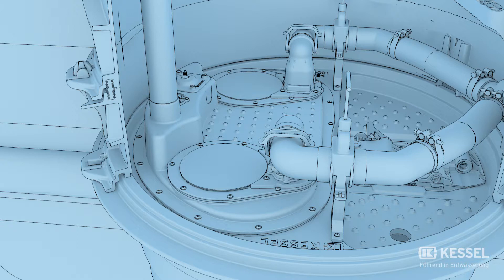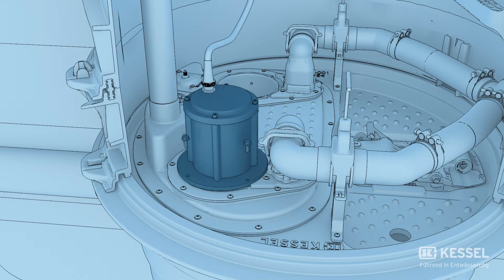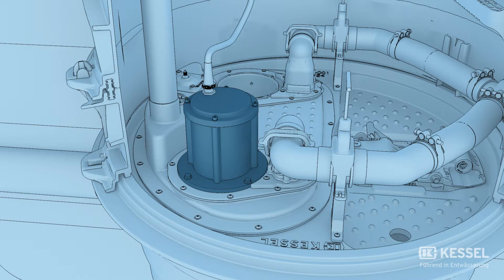First, we remove the construction period protection cover of the pump mountings and fasten the pumps with the bolts provided. The tightening torque may not exceed 7 Nm. Further information can be found in the installation and operating manual.